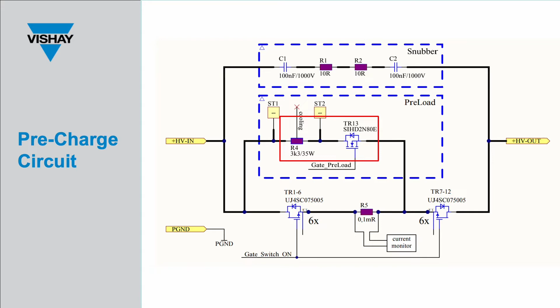During the second stage, the output voltage is measured after 250 milliseconds to see if it has risen to at least 85% of the input voltage. If the total capacitance of the load is excessive, the output voltage will not rise sufficiently, the pre-charge stage is terminated, and an error is displayed. If both the pre-charge stages have been successfully completed, then the MOSFET is switched off and the 12 main power MOSFETs are switched on, as described before, to energize the load.